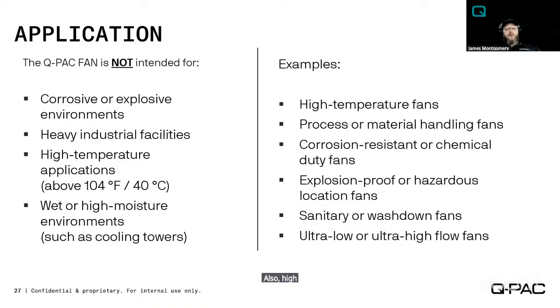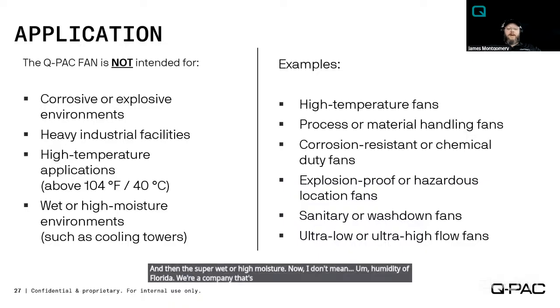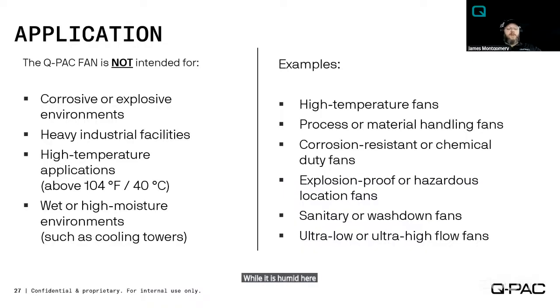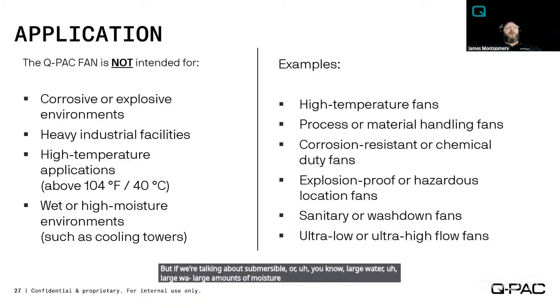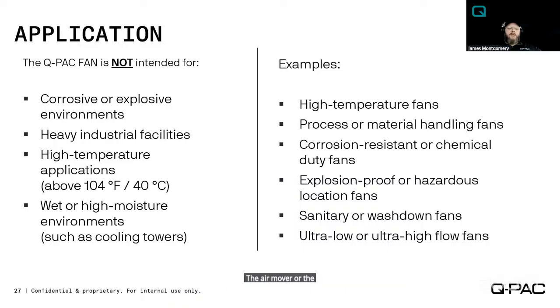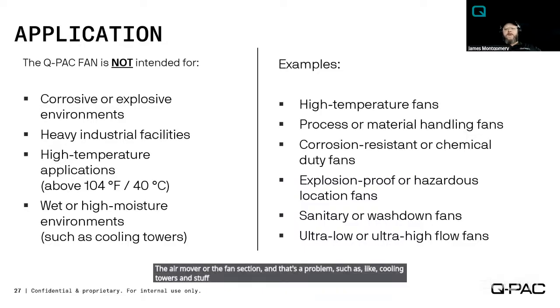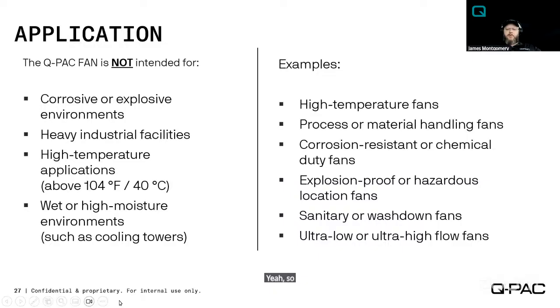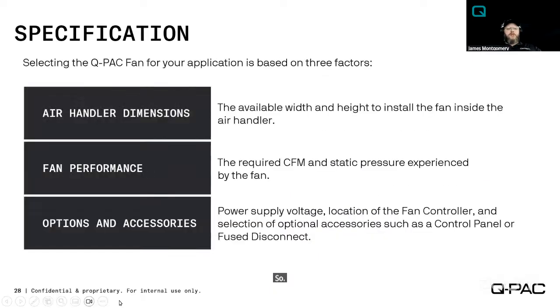Also, high temperature applications, so above 104 degrees Fahrenheit, which is pretty hot for an airstream, or 40 degrees Celsius for those that aren't using Fahrenheit. And then the super wet or high moisture. Now I don't mean the humidity of Florida. We're a company that's manufactured here in Florida. While it is humid here and in other parts of the country, we can operate inside the airstream where that's the typical saturation. But if we're talking about submersible or large amounts of moisture and water being pulled across the air mover or the fan section, then that's a problem, such as cooling towers and stuff like that. Yeah, so I think I kind of went through that pretty well.